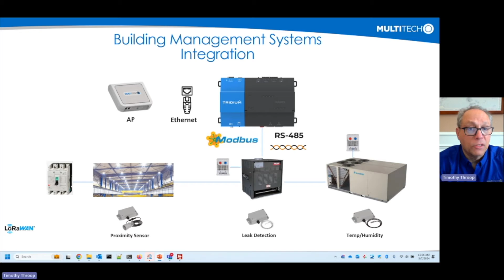Now that you've seen it work, how we attach the devices through LoRaWAN to the Conduit gateway, through the BACnet payload manager, and then onto the BACnet environment, I'm going to take you through that one step at a time. We're going to add one device to the system just to show you how it works.